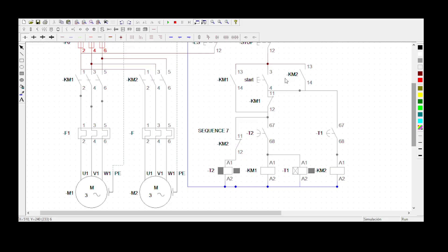We have the holding contact for KM2 and the holding contact for KM1. We have a delay-on timer for KM1, then Timer 1 which is the delay-on timer, KM2, a normally open for Timer 1, a normally open for Timer 2 which is the delay-off timer, a normally closed for KM2, and a normally closed for KM1.